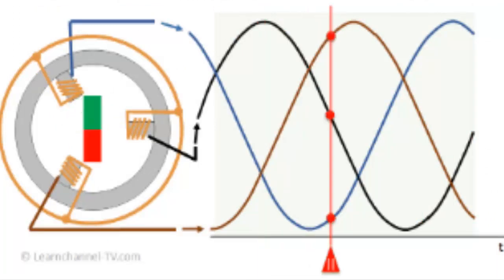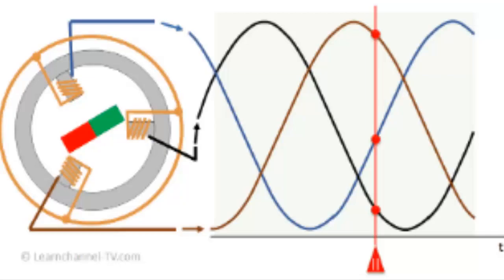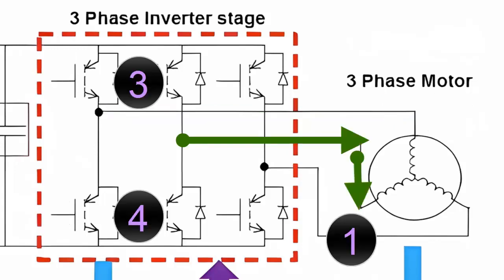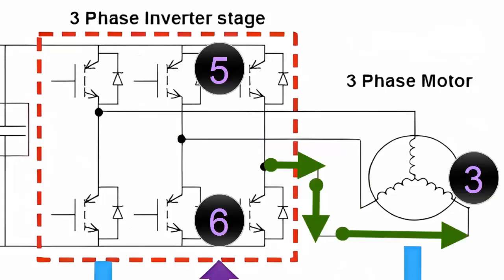3-phase current is alternating, meaning the current in each coil will circulate in 2 directions. Therefore, 2 transistors are used per motor coil, totaling 6 transistors, to supply the 3 compressor motor coils in both directions.